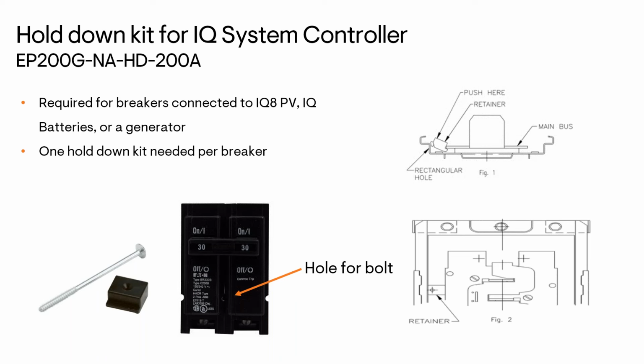I'm not sure I totally understand the question. It sounds like you're describing the sunlight backup configuration where essentially the IQ8 can form a microgrid and power the home even if there's no battery present. Now, for that system to work, there must be a system controller there too, which is essentially the ATS. It does a lot more than an ATS, but it functionally is what you're describing. It disconnects from the utility grid, and the IQ8 can power the home even without a battery. The assumption there being that the home's loads don't exceed the available power from that solar system, which can really vary a lot depending on how much sunshine. And actually, I have a couple of slides that go into how that sunlight backup or daytime only backup system works.